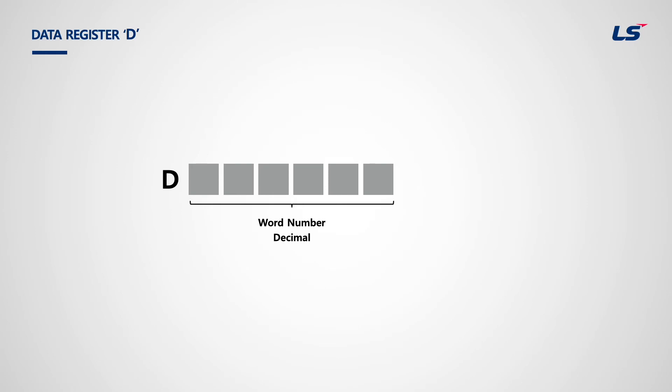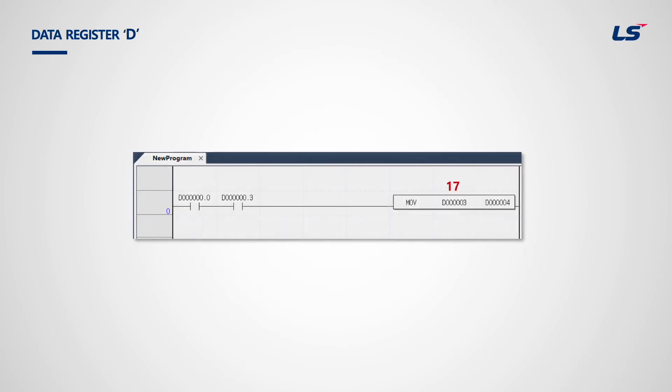The word area is different from bit devices. It is expressed in word numbers only, not used in contact point areas, and is used for calculation and storage of numeric data. However, if users need to use the word area as a bit, they use a period with a hexadecimal value to express the bit. For example, D3 word data is transferred to D4 when D0.0 and D0.3 bits are on.